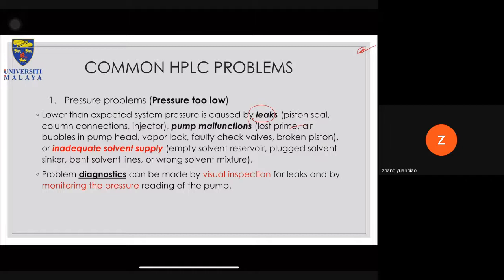All right, so there might also be air bubbles in the pump head, or vapor lock, which is very, very unlikely, but can happen. Faulty check valve or a broken piston. Normally, if a piston is broken, you will hear a very loud noise. Also in the liquid solvent supply: an empty solvent reservoir, plugged solvent sinker, bent solvent lines, and wrong solvent mixture. So a lot of things can happen if the pressure is too low.